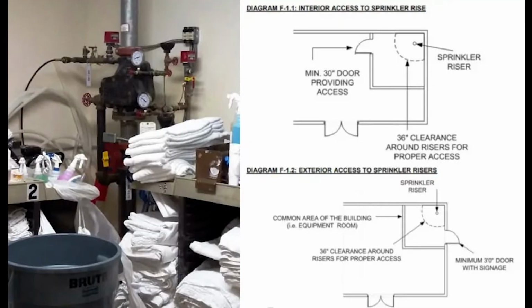A common fire code infraction is that of cluttering of fire sprinkler rooms. The room is not a storage room. Extra items in the room are not permitted because they can slow someone down while accessing valves during an emergency. The 2018 edition of the International Fire Code requires 36-inch clearance around the risers for proper access. These are just some of the requirements for designing a high-quality fire suppression system. These requirements are all based on the applicable fire code books.